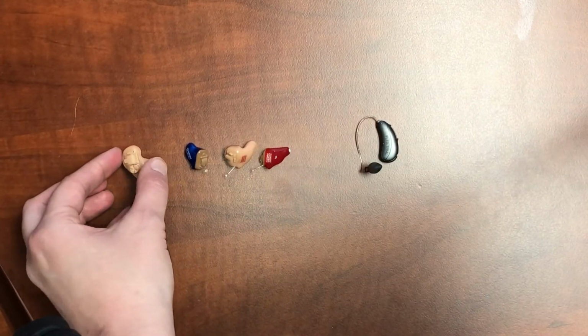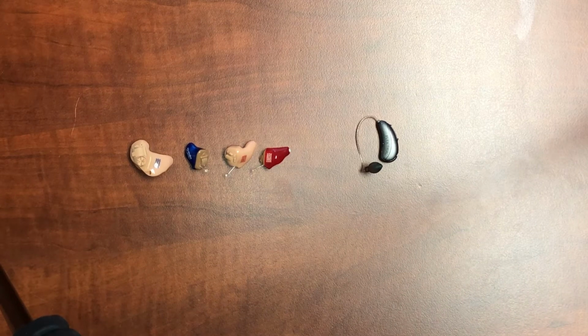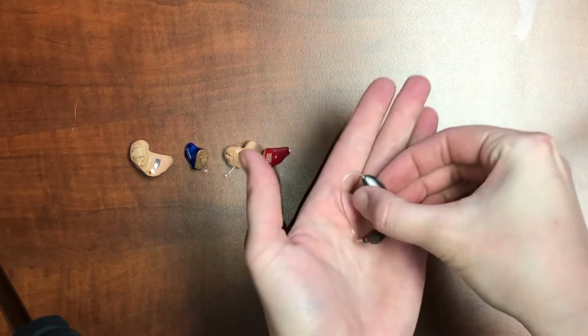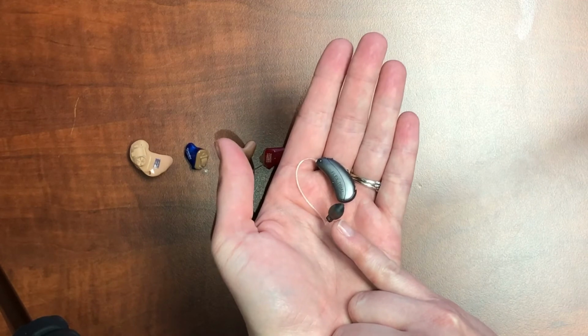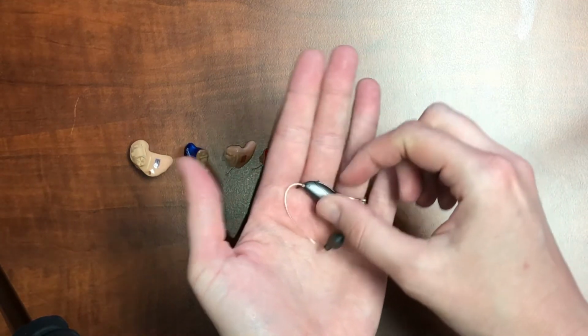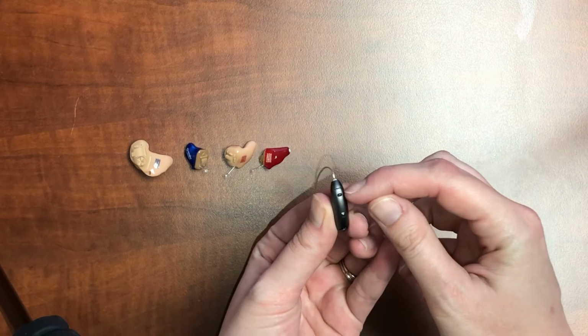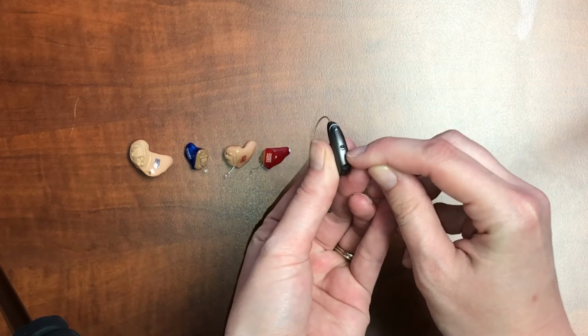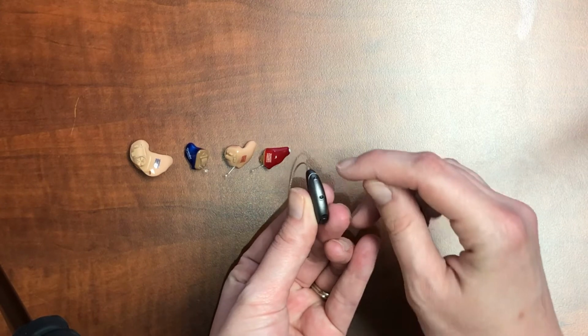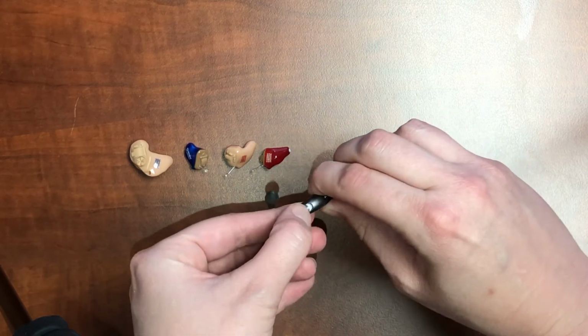Now, not all hearing aids will have different controls like a push button or a volume wheel. It really depends upon each type, but all hearing aids will have the microphone, the sound bore, and either a battery door or some sort of power source if they're rechargeable. For the behind the ear style, you have the earpiece here. There is this wire that connects to the hearing aid. On the back, it's hard to see, but there are some slits here and here, which are the microphones where the sound comes in. There's a volume control, and then down here is the battery door.